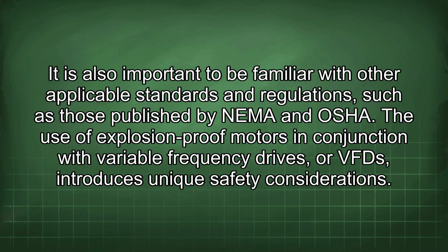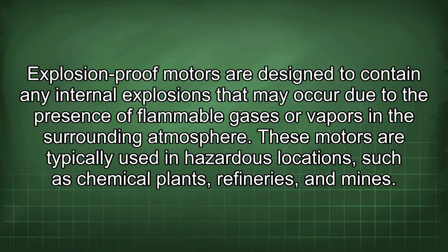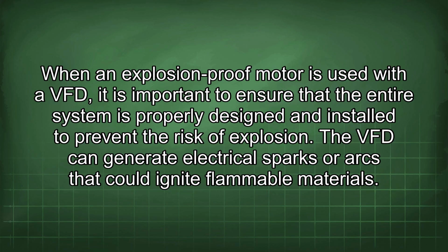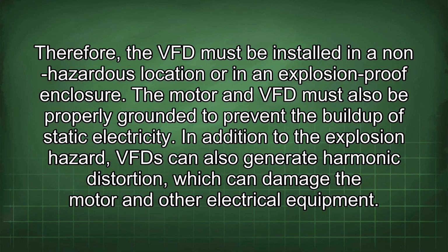The use of explosion-proof motors in conjunction with variable frequency drives, or VFDs, introduces unique safety considerations. Explosion-proof motors are designed to contain any internal explosions that may occur due to the presence of flammable gases or vapors in the surrounding atmosphere. These motors are typically used in hazardous locations, such as chemical plants, refineries, and mines. When an explosion-proof motor is used with a VFD, it is important to ensure that the entire system is properly designed and installed to prevent the risk of explosion. The VFD can generate electrical sparks or arcs that could ignite flammable materials. Therefore, the VFD must be installed in a non-hazardous location or in an explosion-proof enclosure.